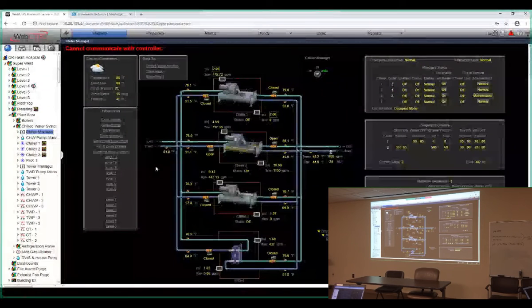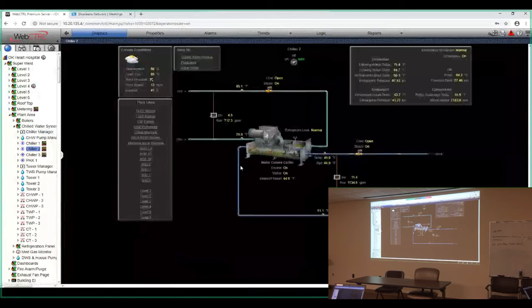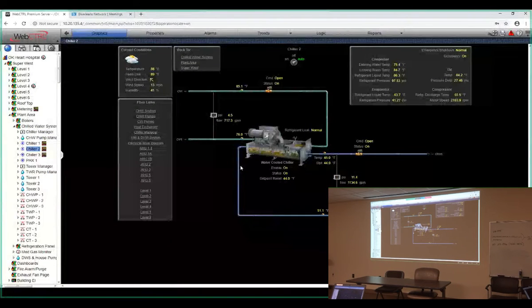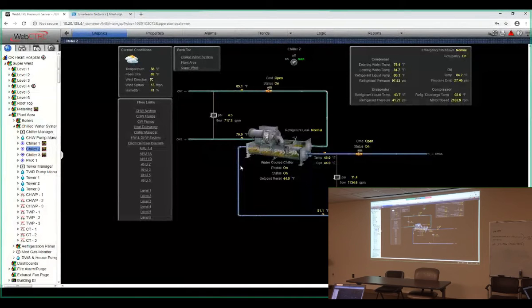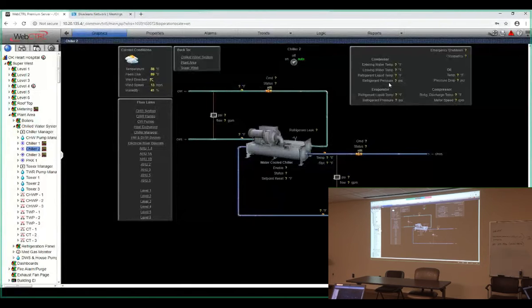So let's look at chiller 2. Okay, so as we drill down into the system, what we're doing is just looking specifically at each component. So it's the same information, we're just showing you more of it. Not the same information. More information about a component. That top right area are the integration points that we're pulling in. So we've got entering water temp, leaving water temp, refrigerant pressure, liquid temp, refrigerant pressure, our refrigerant discharge rate, temperature, and our motor speed.